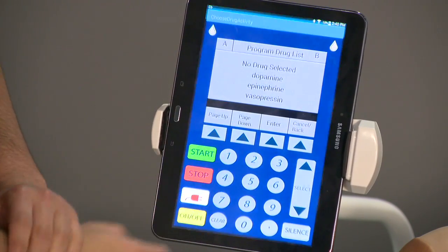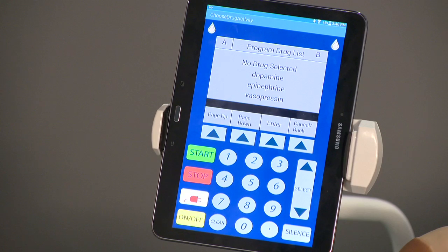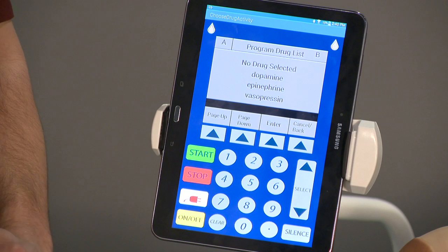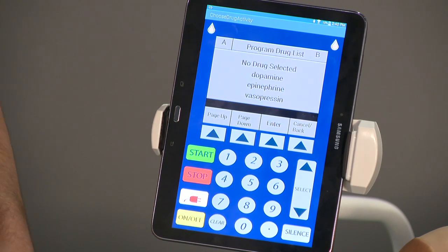Once you do that, this screen shows you what we received from initialization. This list with 3 drugs we received from the software controller. So basically, this is where that populated list went during initialization. Obviously, initialization is very important because if that step was messed up or skipped, there would be no drug list and there would be no drug infusion. Nothing would be working because we would have nothing to infuse.